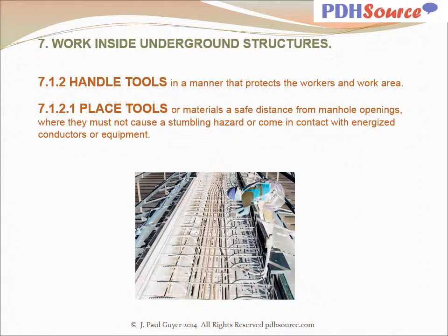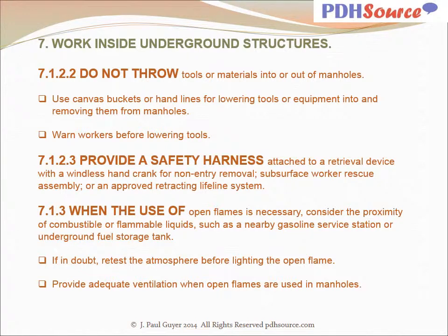Handle tools in a manner that protects the workers and work area. Place tools or materials a safe distance from manhole openings where they must not cause a stumbling hazard or come in contact with energized conductors or equipment. Do not throw tools or materials into or out of manholes. Use canvas buckets or hand lines for lowering tools or equipment into and removing them from manholes. Warn workers before lowering tools. Provide a safety harness attached to a retrieval device with a windlass hand crank for non-entry removal, subsurface worker rescue assembly, or an approved retracting lifeline system.